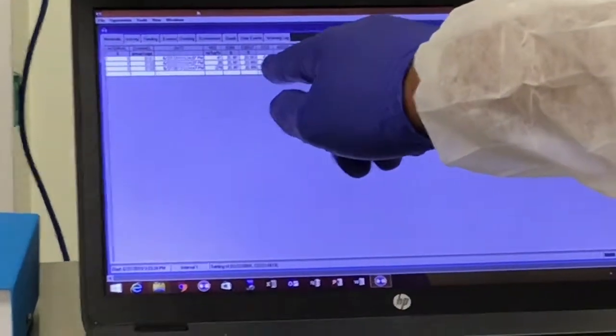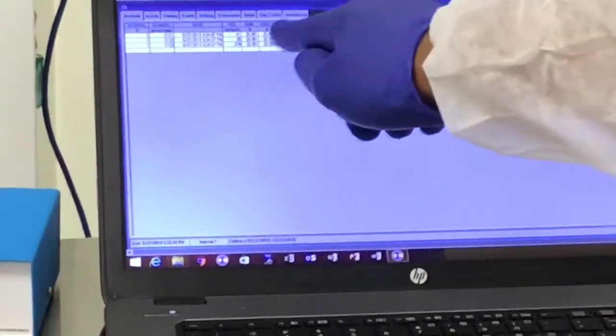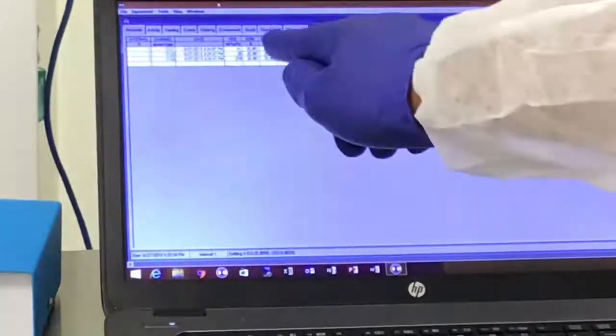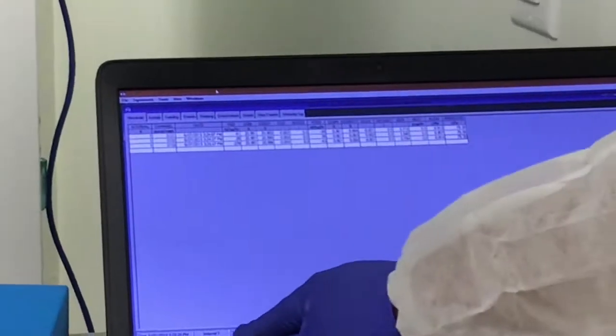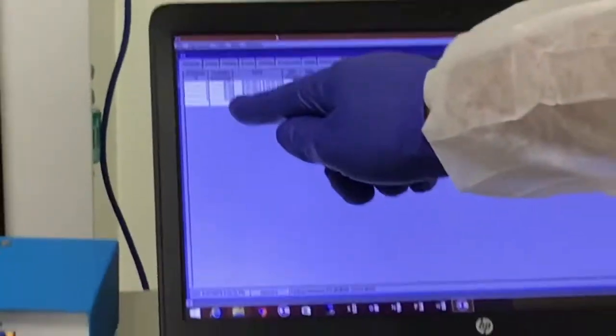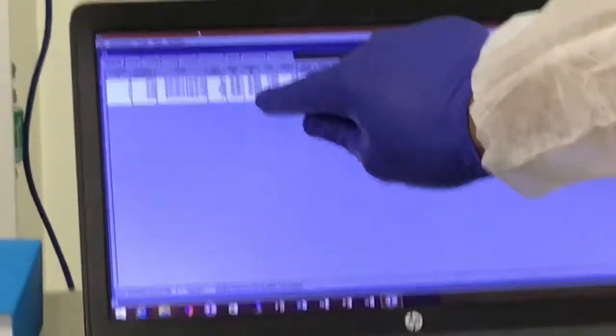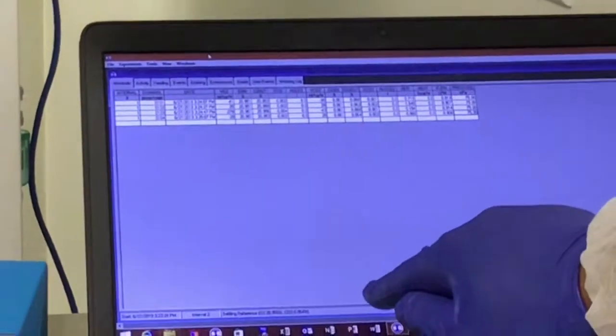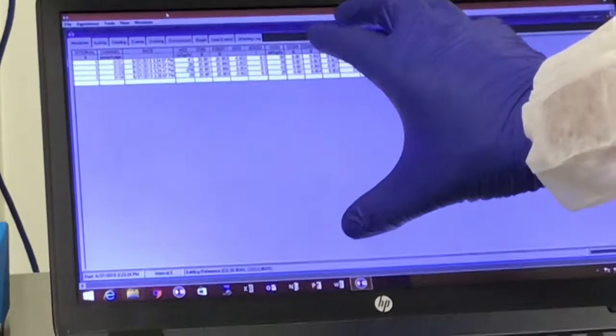So we're going to go through one cycle. Next time it goes to 1, I am going to be breathing on cage 1, and let's see the difference between the first reading on cage 1 and the next reading on cage 1. So now it's settling 4. We told it to reference every 4 cycles. So once it does 4, guess what? It's going to do reference, room air again. And if anything changes in the room, your in will change. So if you have people coming in and out, you want to reference often. If there's no one, there are not many changes, so you don't have to reference as often. That's what it means. If we had chosen 16, it would do 16 samples, then reference.